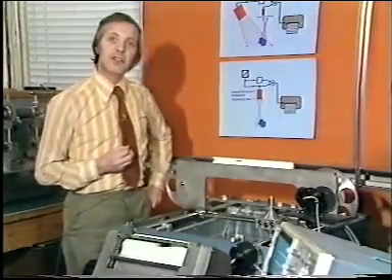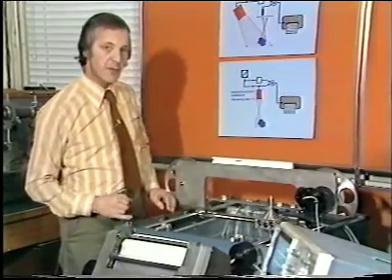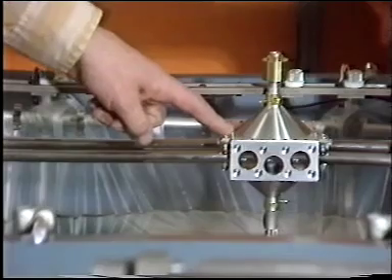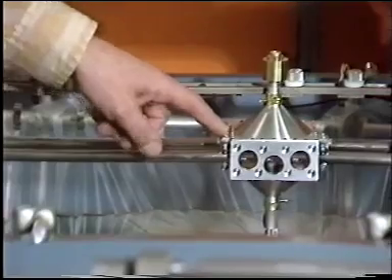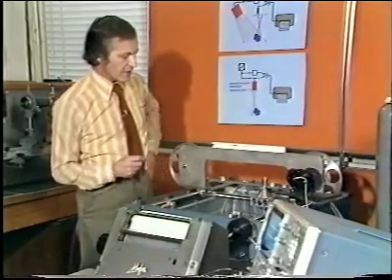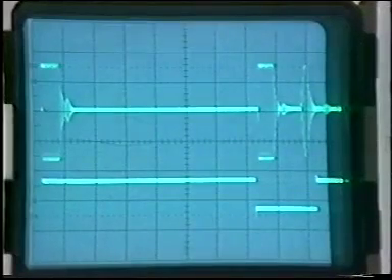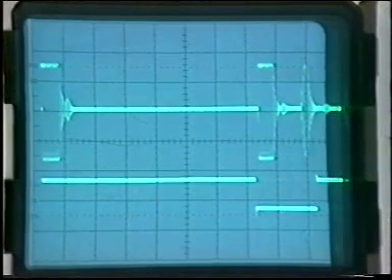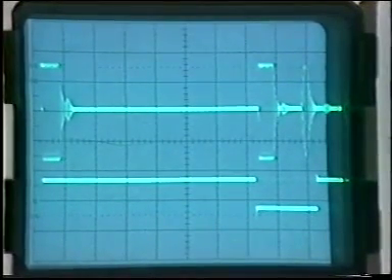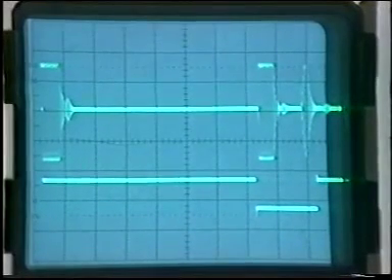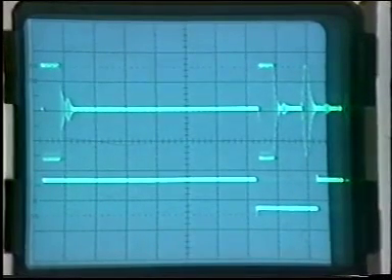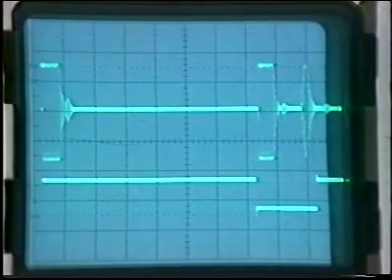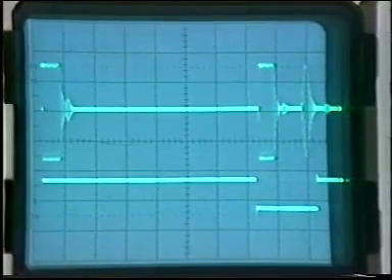Okay, well, let's look back at the tank again. As I was saying before, we have a carriage below which there's a transducer. And at the moment, it's not moving. If we look at an oscilloscope, we can see a conventional A-scan display from this transducer. On the left-hand side is the transmitter pulse, and then there are two big ones on the right-hand side, the first of which comes from the top surface of the block, and the other one from the bottom surface. On the lower trace, you can see a time gate which selects out the echoes in the region of the block and enables us to suppress echoes which might be bouncing around in the rest of the tank.